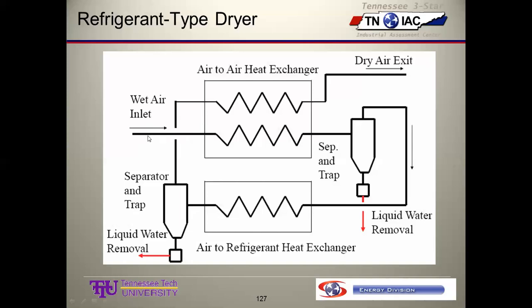So, we've got energy coming in, we've got this warm air stream we really want to cool down. Our point is to cool this to 35 to 38. On the other side, we have air that has been cooled in the air coil or the heat exchanger down here. So this is cold, 35 to 38 down here. This is just a separator. So we've got cold air here we want to heat up, and hot air here we want to cool down, so it's a perfect application for a heat exchanger. The cold air comes in on this side and picks up heat from the hot, moist, compressed air coming out of the air compressor. So this gets cooled down and this gets heated up, and everybody's happy, I guess. Then this is the nominally 60 degree air, 65, whatever, that goes out to the plant or maybe to a filter or something before we send it out. And this is the pre-cooled compressed air, which is now lower in temperature.